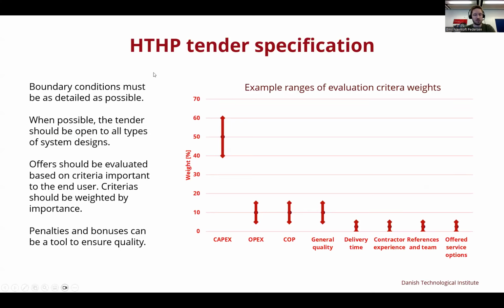Some of the most important things are that you must specify your boundary conditions of the heat pump, so your sink temperature and source temperature, and the medium flow rates, as clearly as possible, along with the variations that can be expected. You should not limit your tender to specific system designs; it's best to give the supplier freedom to design the most optimal system.